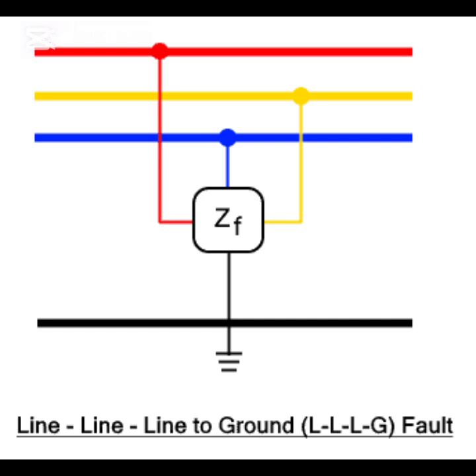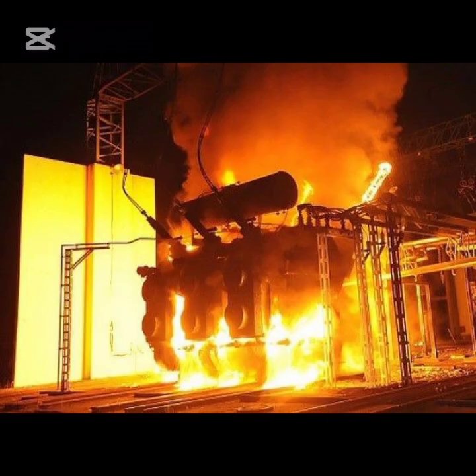Example: a major fault where all three phases come into contact with each other and also make contact with the ground, such as when a transformer fails, or all broken lines touch the earth. This is the most dangerous type of fault and can cause significant damage to equipment and systems. The presence of a ground path added to the phases shorted results in the highest fault currents. These can cause fire and system shutdown.